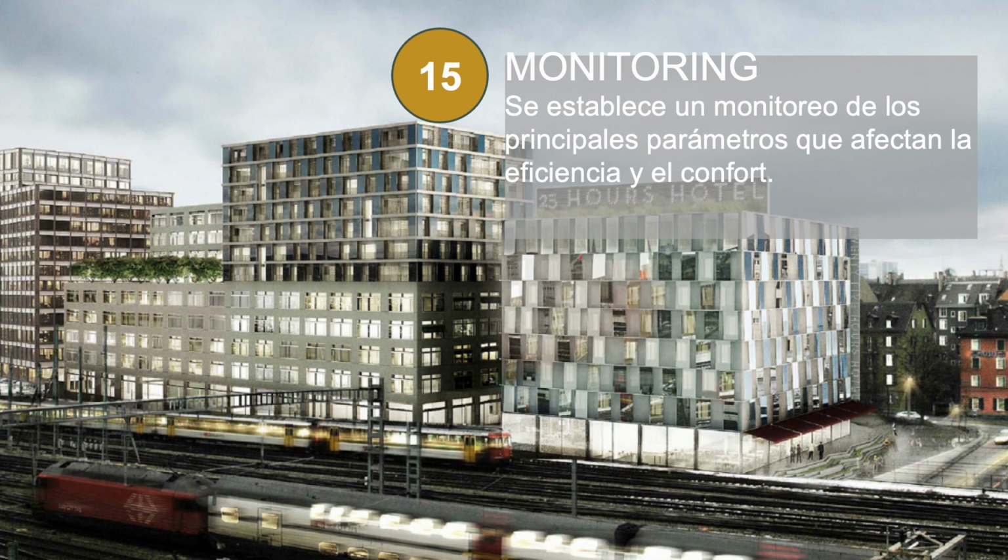Therefore it was mandatory from the beginning to install the framework of sensors and measuring equipment to constantly measure the energy flows in the building, frequently and automatically analyzing the performance and comparing it to the expected benchmarks. So the operation team is able to react when the performance leaves expected boundaries, and it allows them to detect failures and unexpected user behavior early. And that builds the basis to rely on and maintain a net zero building in operation. This is something which is very important if we come close to net zero buildings.